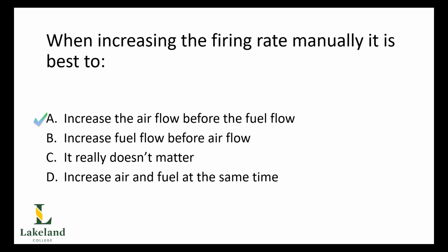And whenever making manual adjustments to a combustion controller, of course, we want to walk it up and walk it down nice and gradually. Don't do big adjustments. It's not good for the boiler and it's not good for the metal itself that's being stressed now by higher firing rates. You will have a tendency to swing your boiler, which means you will induce swell and shrink.